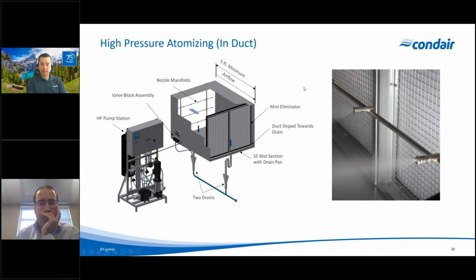Now, the thing to consider here is because we're actively spraying the water, we do need some time for that water to absorb into the air, evaporate into the air. So generally, we try and design around a 5-foot minimum duct section or air handler section to achieve a decent amount of evaporation. We can go as low as about 3 feet, but in those cases, we're probably wasting 50, 60, 70% of the water that we're spraying into the air. So just something to keep in mind for retrofit applications.